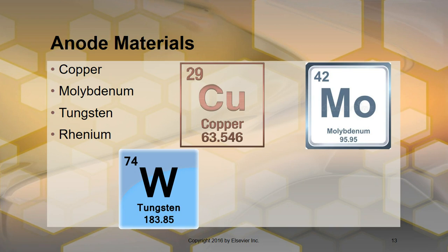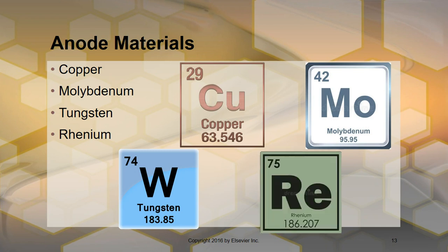Now, with the tungsten, pretty much all of our newer tubes today use something called rhenium. Now, rhenium is just one step above tungsten, but it is sometimes mixed with the tungsten so that it increases the capacity and the tensile strength, which means that it keeps it from getting hot and deforming from the heat. So if you ever have melted a penny or something and you saw how it kind of gets wavery, it floats around, that's what would happen if you used just copper. So that's why you use all of these materials. So those things are very important to remember.